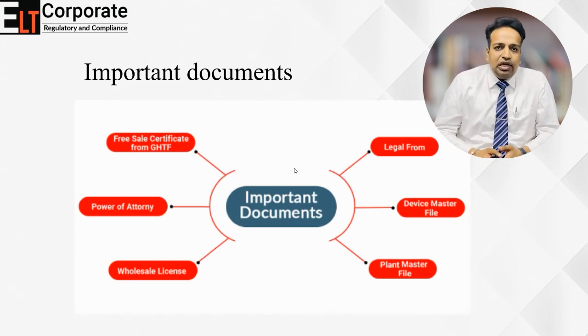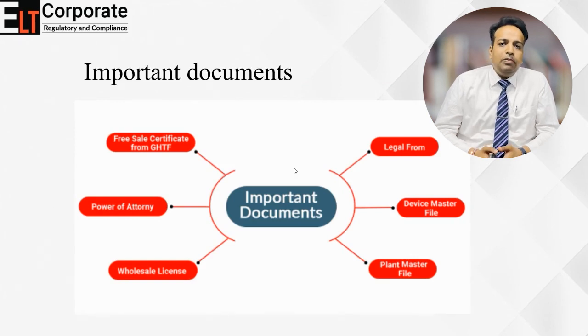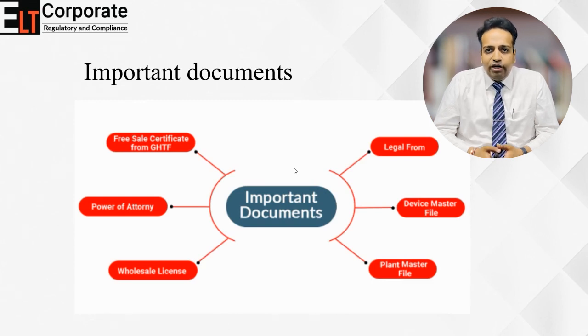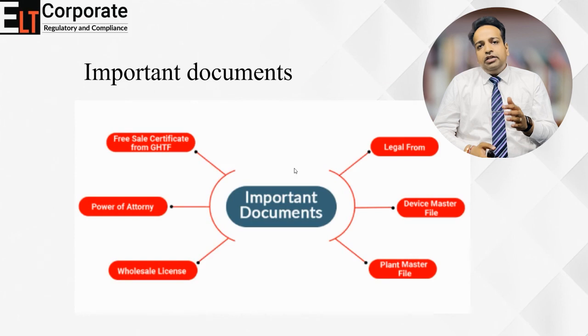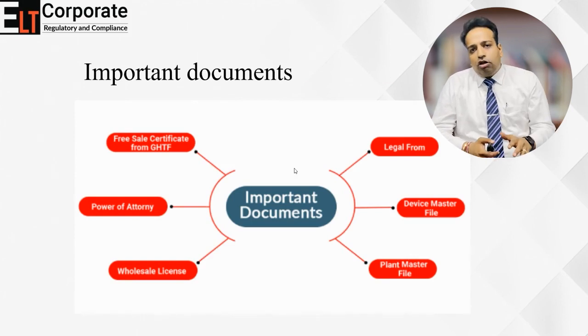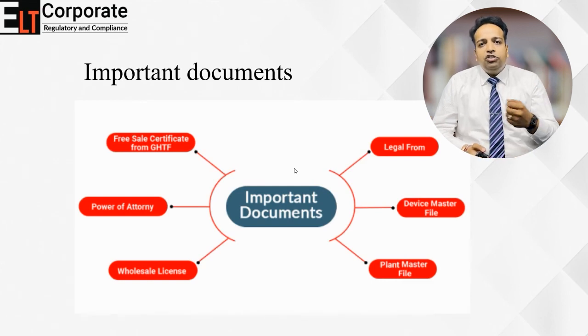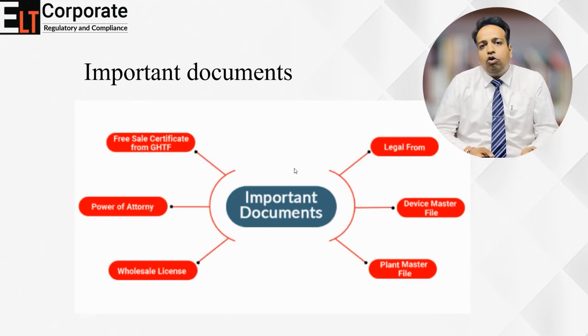A wholesale license — essentially a selling and distribution license — is also required, which you will obtain from your local state under Form MD-42. Additionally, a Plant Master File and Device Master File need to be provided by your supplier. A legal form is generated once you submit all the documents; you need to print it, digitally sign it, upload it back, and then finally pay the government fee.